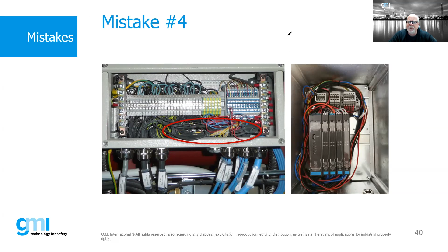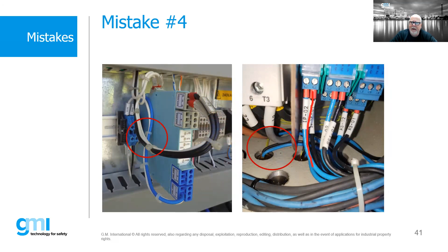Same thing here. These are two different real world examples, right? We have IS over on the right-hand side in the picture over here where we have protection coming out, protection coming out. We have power over here. We have a separation, but now we've taken our IS circuits and obviously we do not meet this 50 mil separation between the power and the IS. You can barely see this, but that's actually a barrier gland that's sealed. So the solution here to remove that is not an easy one to take advantage of, right?